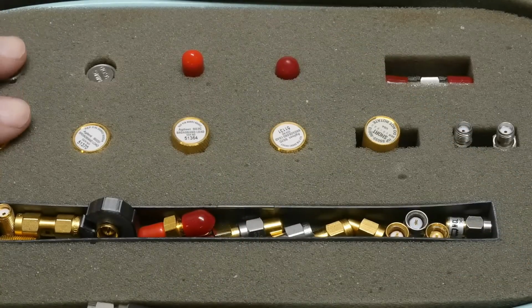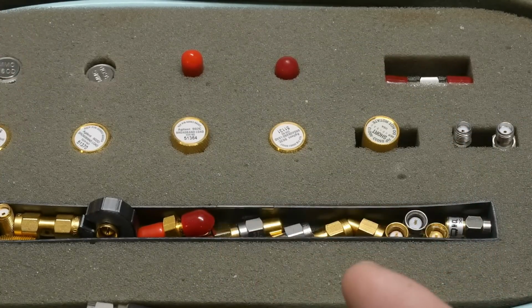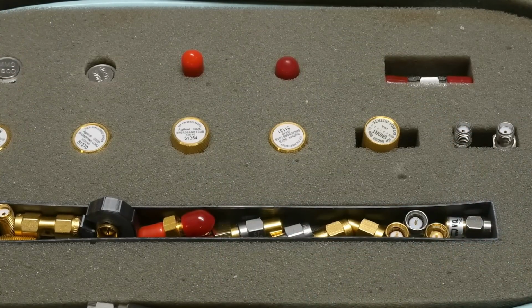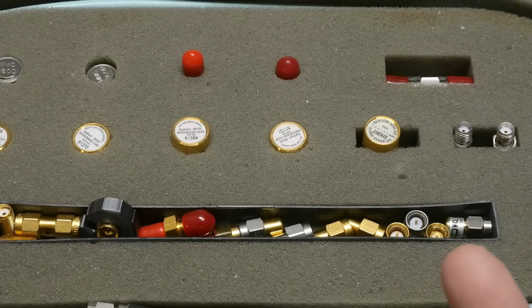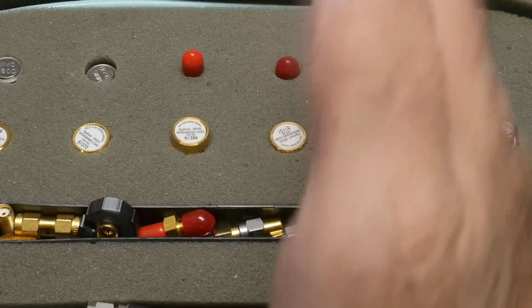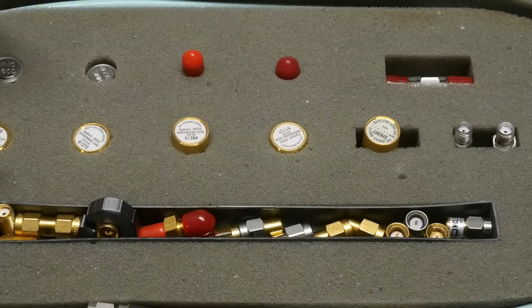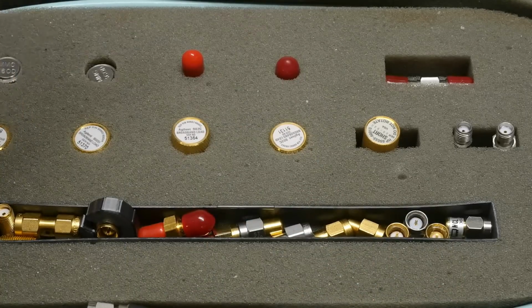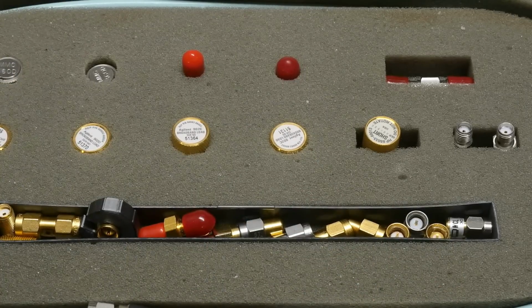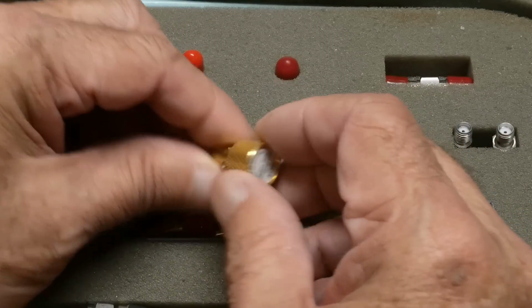Strangely enough, it doesn't require opens. So when you calibrate the machine, I'll show you this in a second, but when you calibrate the machine, it doesn't ask you for an open, it just uses the open. So when it's actually doing the reference plane, we'll talk about reference planes. When you're doing the reference plane analysis, it's done with the short. Okay, that sets the exact plane. All right, so those are the females, and then there's males.